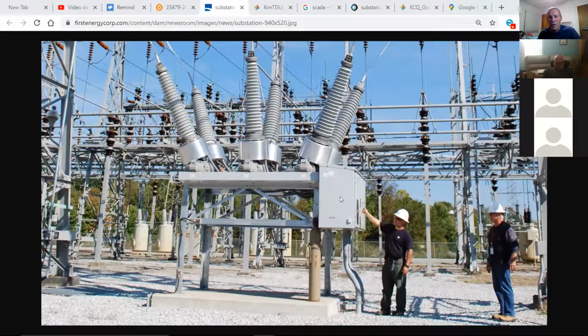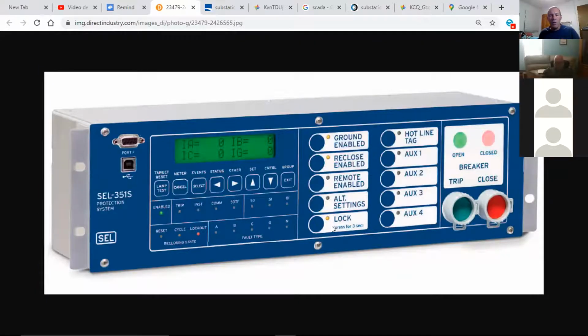I can control it manually on this side of this box. Once I take local control, usually it stays in remote, and that interface is going down through here underground to either a radio tower or a fiber optic interface. Now, if you switch this thing to local, can Scada still take back over control and turn it back to remote? Not until you, great question, not until you give it back to remote. So you have to manually transition it back. Once I have unlocked it, now they know I've done it. Once I have unlocked it, press and hold for 3 seconds.